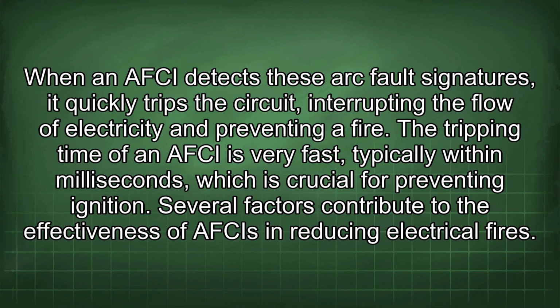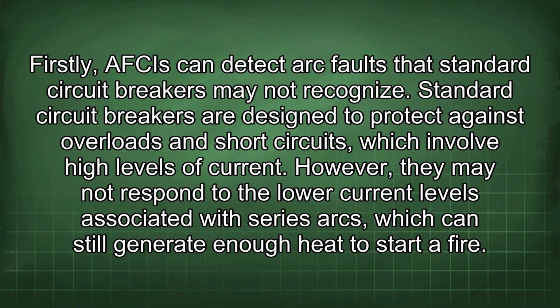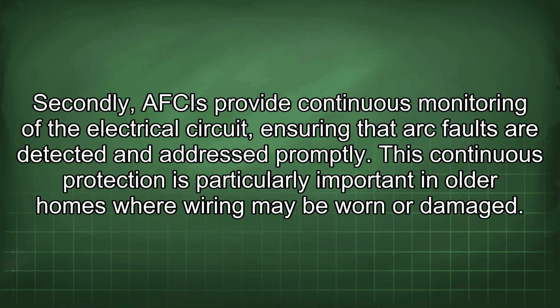Several factors contribute to the effectiveness of AFCIs in reducing electrical fires. Firstly, AFCIs can detect arc faults that standard circuit breakers may not recognize. Standard circuit breakers are designed to protect against overloads and short circuits, which involve high levels of current. However, they may not respond to the lower current levels associated with series arcs, which can still generate enough heat to start a fire.